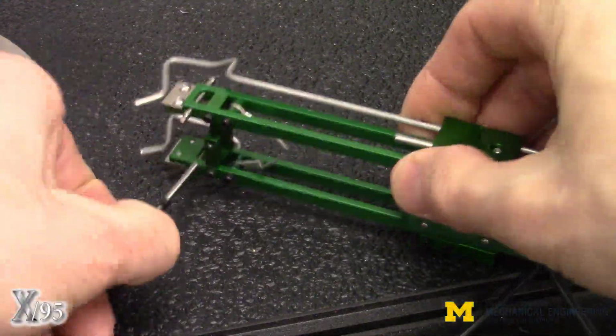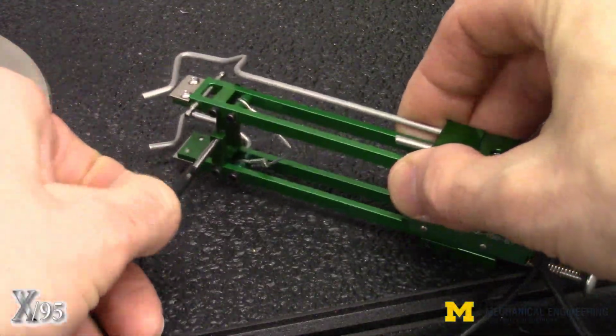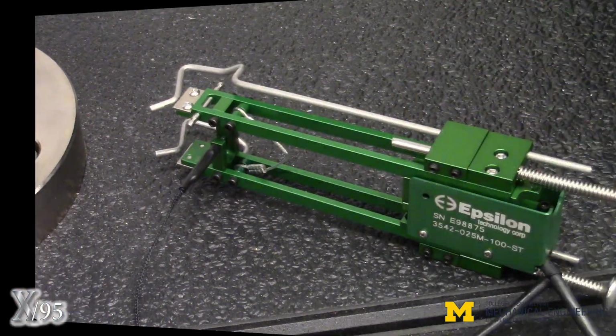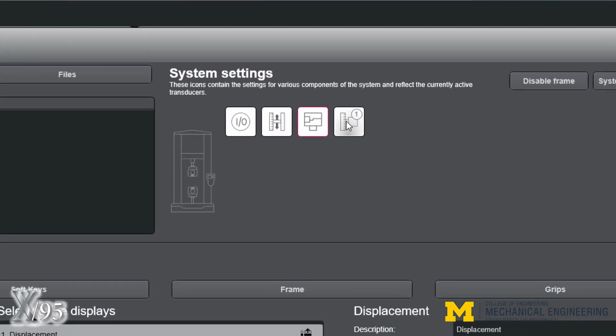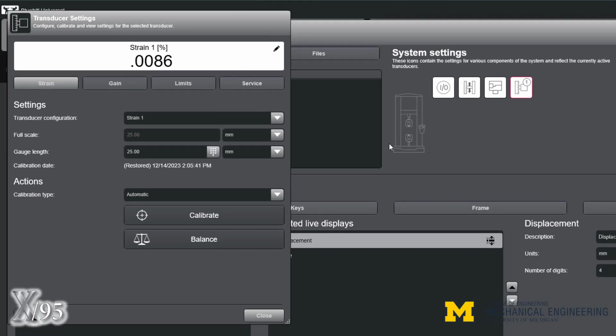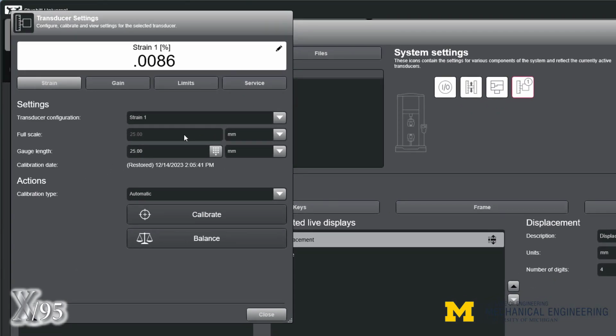Install the calibration pin in the extensometer to set the gauge length to 25 millimeters. In Bluehill, click on the Strain 1 icon, which opens the calibration window. Verify Strain 1 is the selected transducer, then click the Calibrate button.